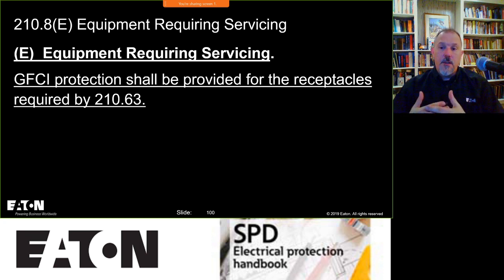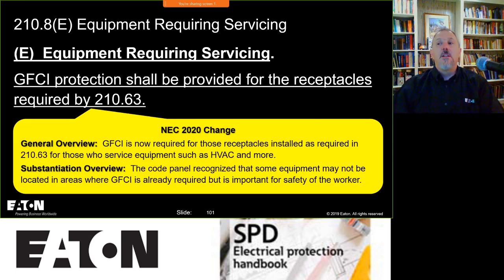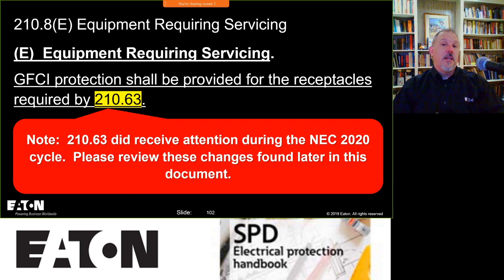Equipment requiring servicing - another important change for the electrical worker working on equipment that might be in a location that doesn't already require GFCIs. For example, if my HVAC equipment is in the basement, it needs GFCI protection on all receptacles, so I'm covered. If equipment is outside and I'm required to put a receptacle there for servicing, it already has to have GFCI protection. But there are places where equipment requires servicing that may not have GFCI requirements currently - if you have a receptacle there for maintenance purposes, it's now going to need to be GFCI protected.